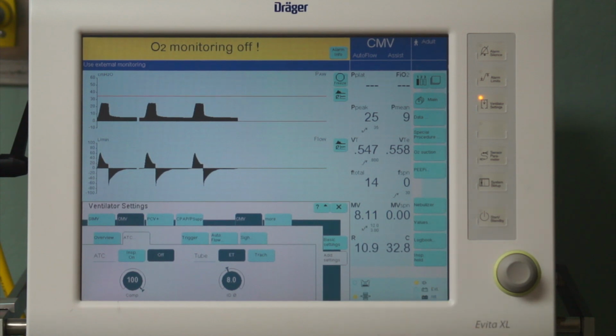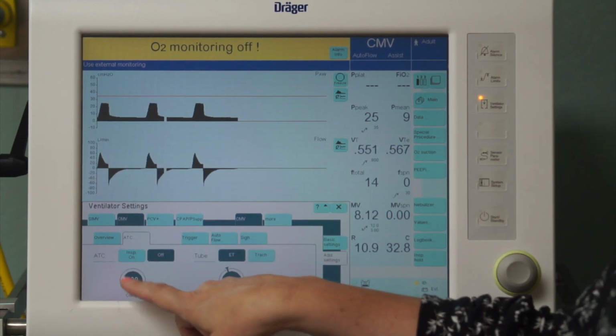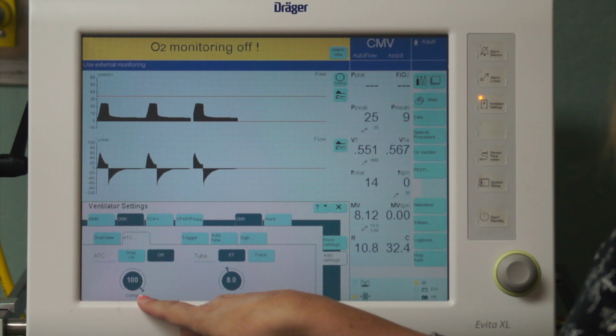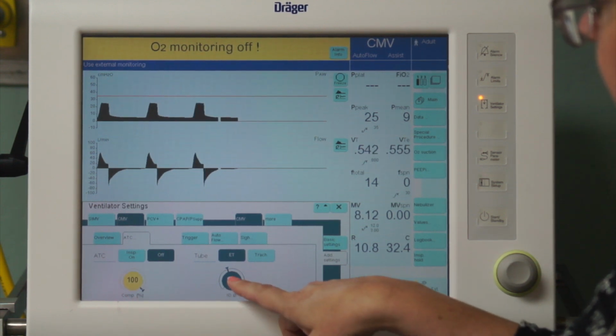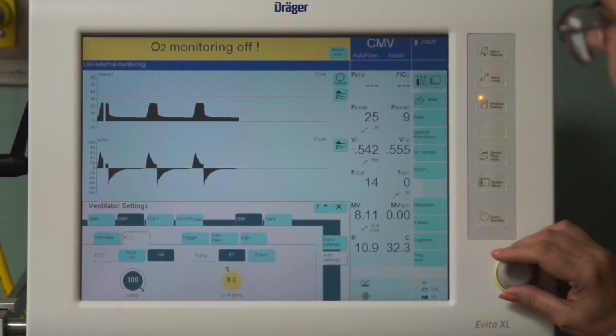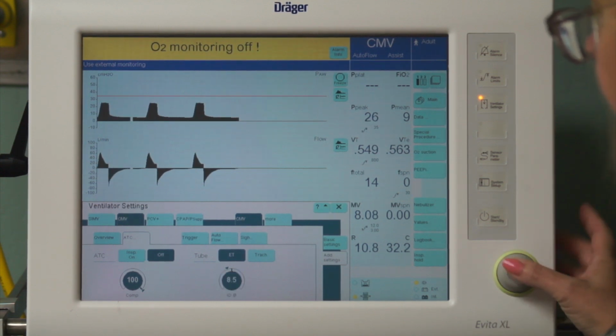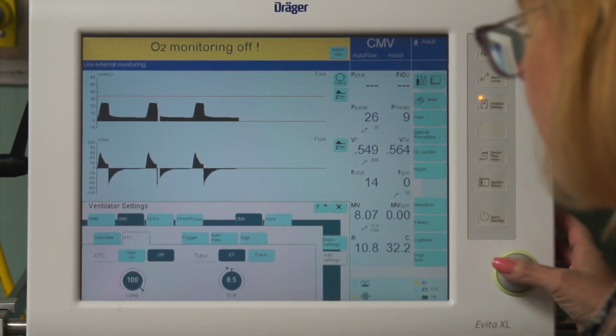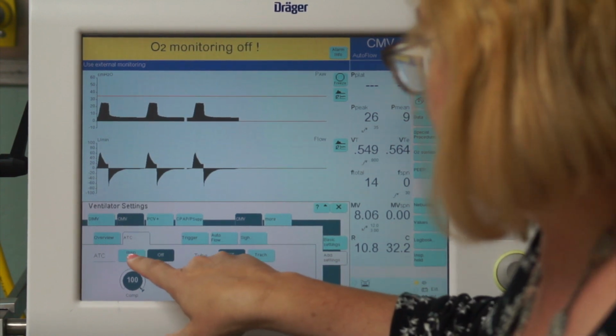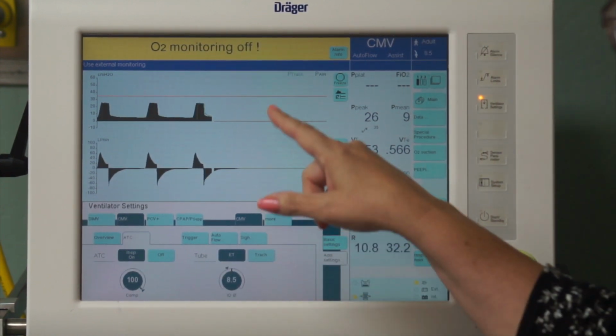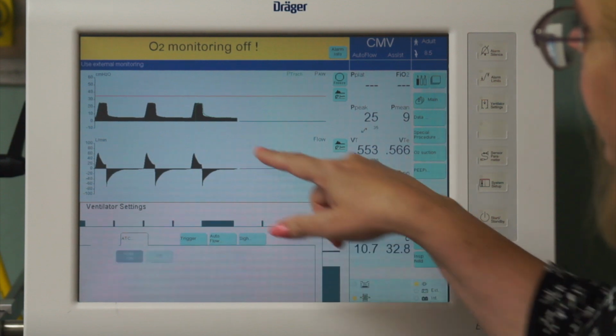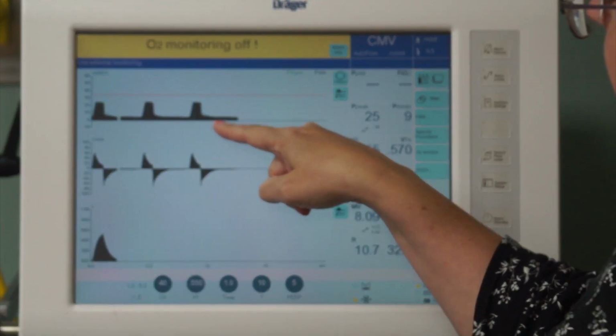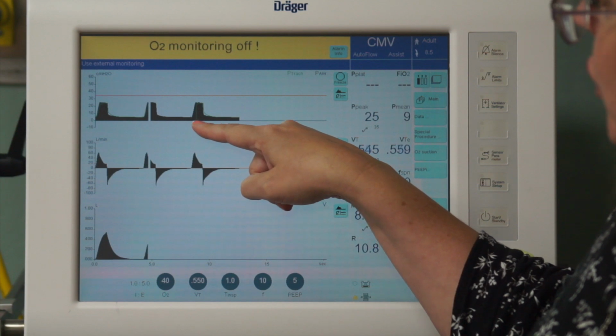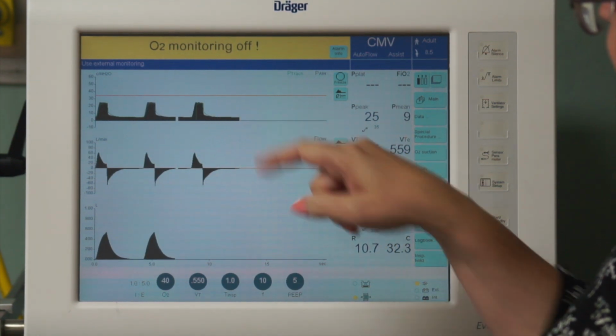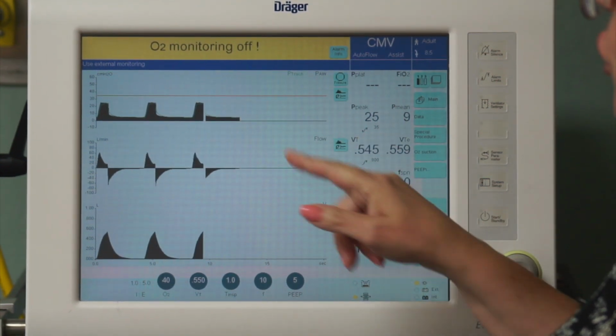So this will automatically compensate for that. And you can choose how much compensation you would like to do. So if we chose 100%, and we're going to choose this size tube, 8.5, right? And if I turned it on, we're going to notice that this changed my waveform a little bit. See that little bit of green that's going around here is the tube compensation. It didn't really change anything too significantly for this patient.